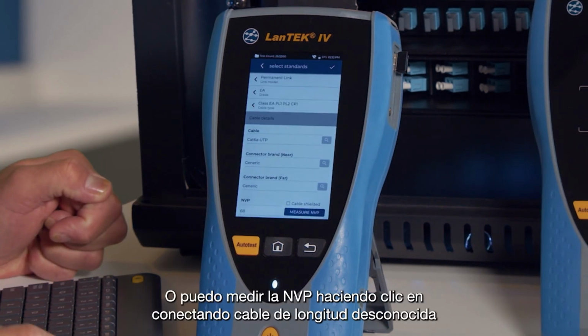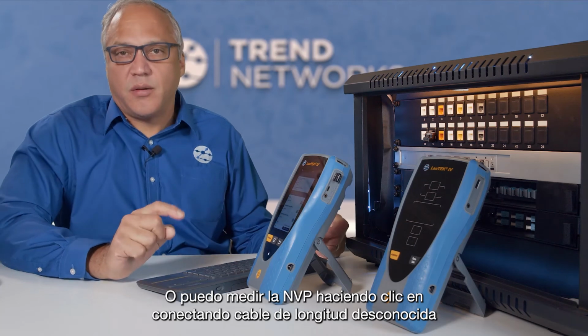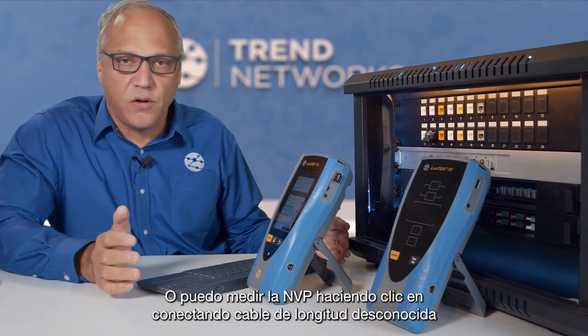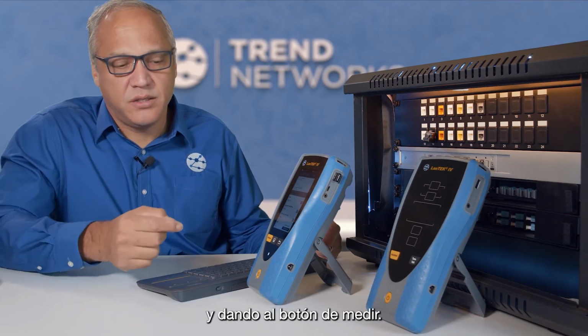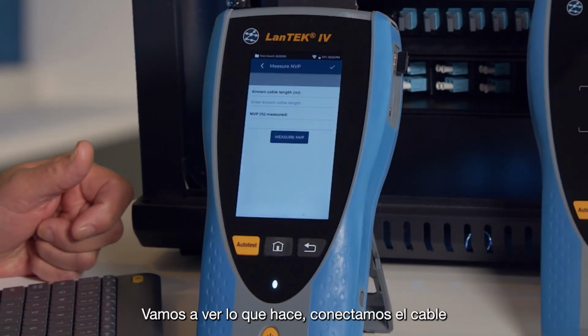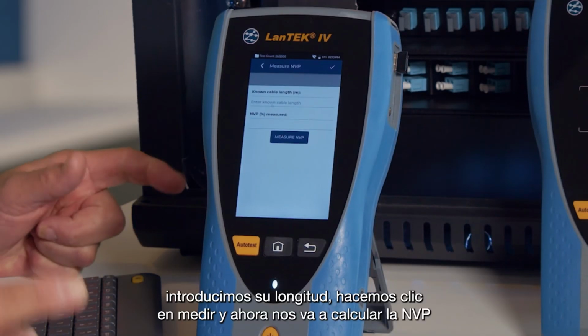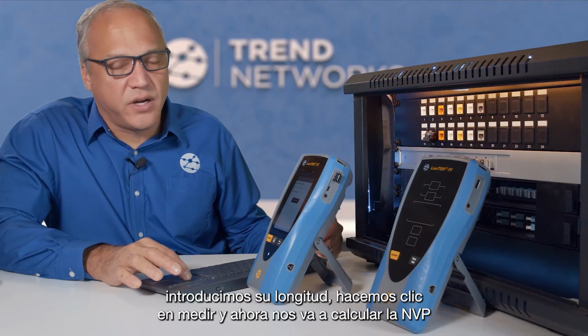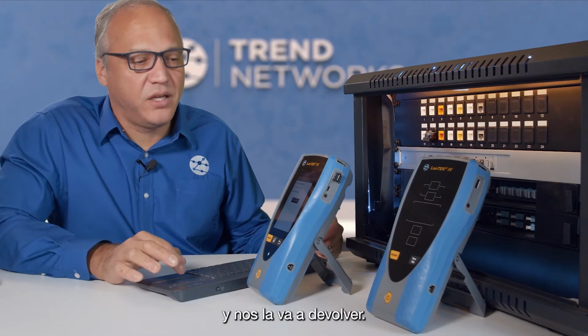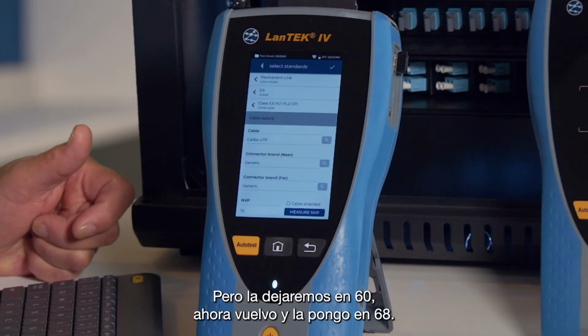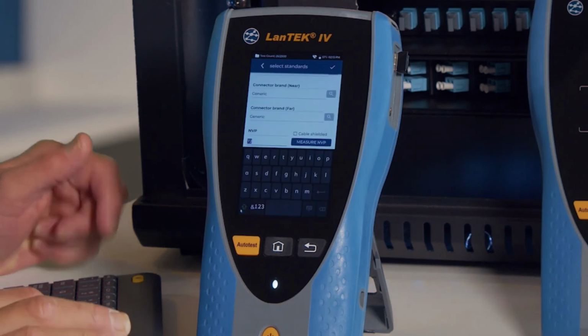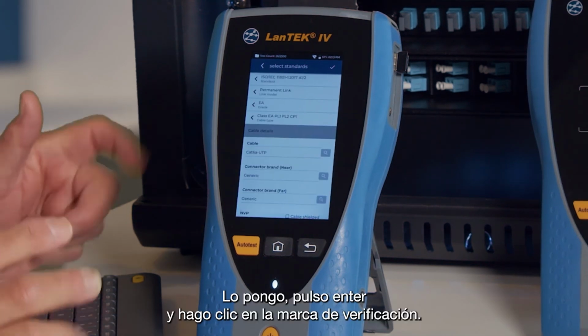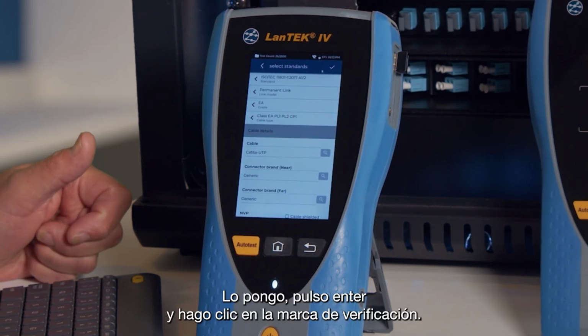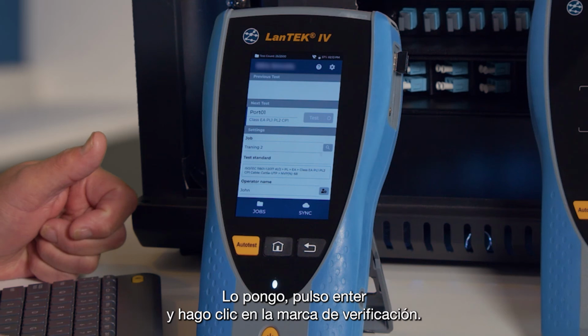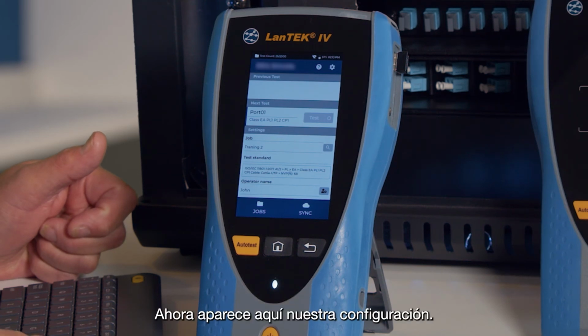Or I can measure the NVP by clicking that, connecting a known length of cable, and hitting the measure button. So if we look at what that will do, we would connect the cable, enter the length of it, click measure, and then it will calculate the NVP and feed that back to us. But we'll just leave it at 72. We'll go back and set that to 68. 68, enter, and hit OK. So now our configuration is shown here.